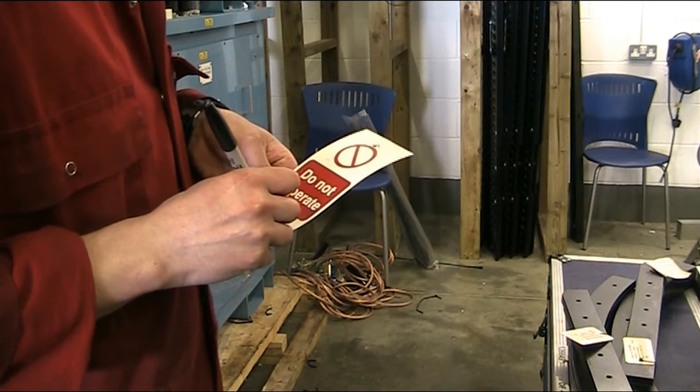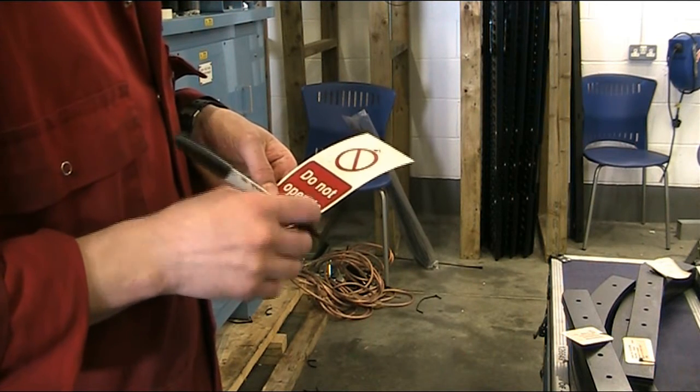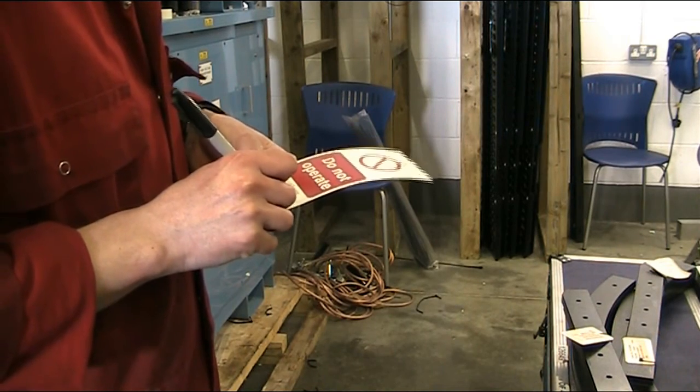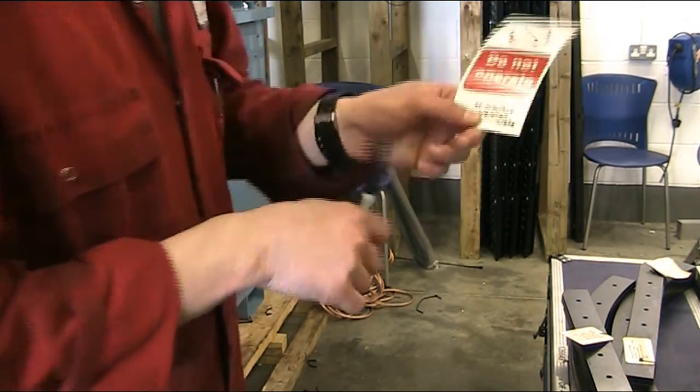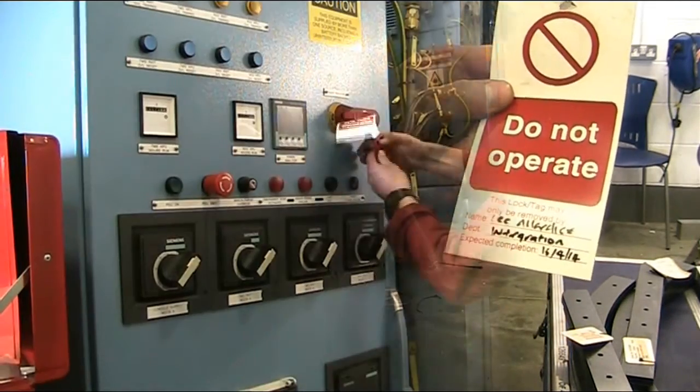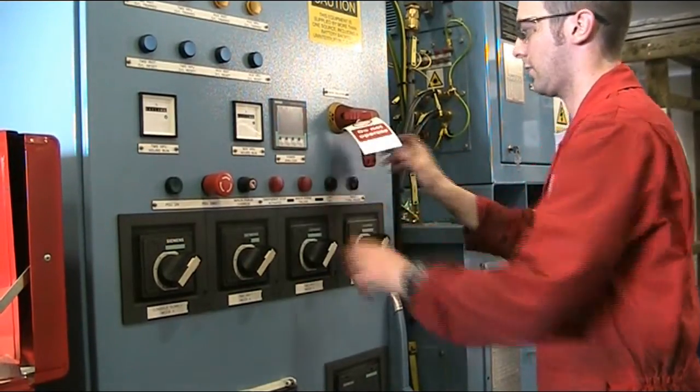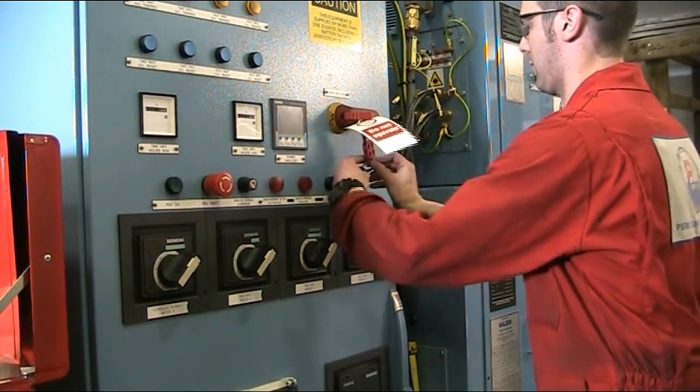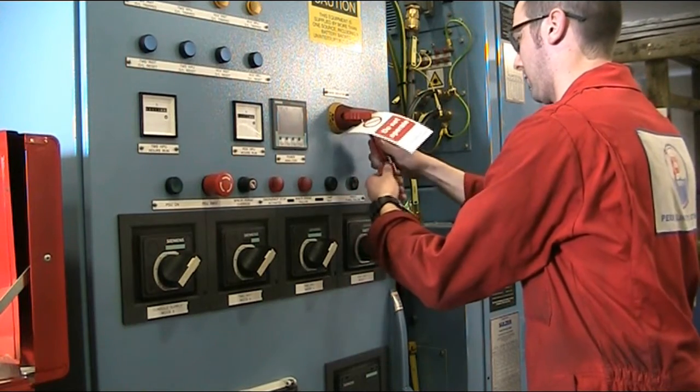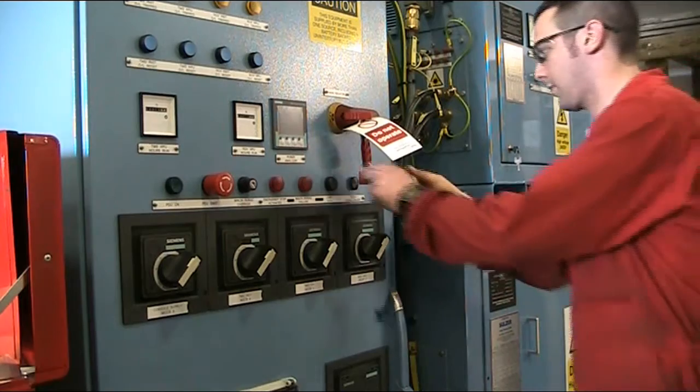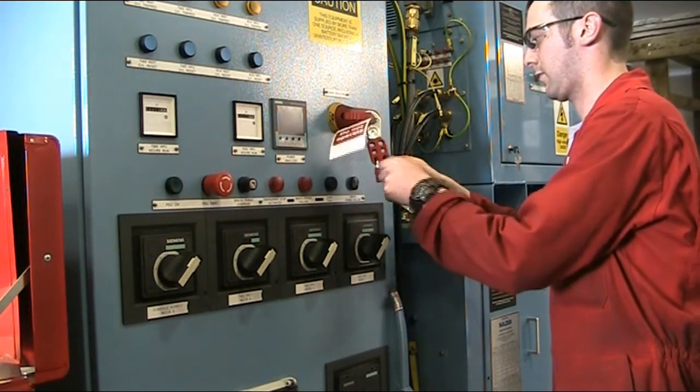We will now see the engineer switching off and isolating the power distribution unit by attaching padlocks to the main breaker. Warning labels recording the time, date, permit to work number, and a brief description of the nature of the work are attached to the lock off point. Exact procedures vary but a two lock system with the worker applying a lock and the supervisor or person in charge of the work applying a lock is generally accepted as best practice.